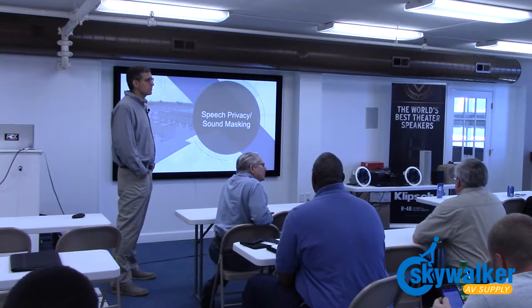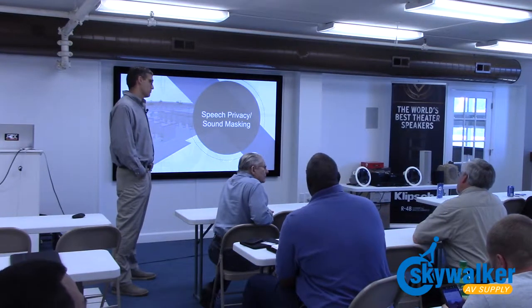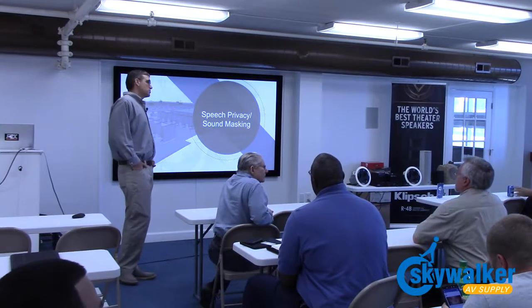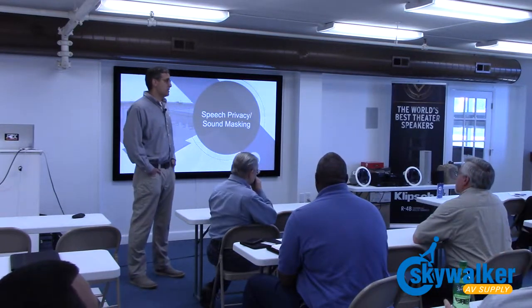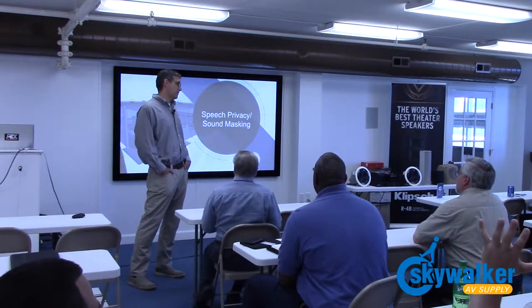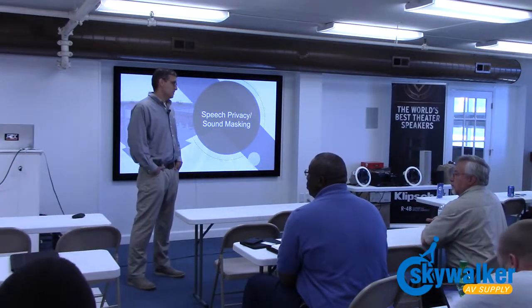When you're talking about the 70 volt there, as opposed to just running low voltage wire to two channels, is that all in the receiver that's doing that? Where is it starting? The amplifier starts with a 70 volt output. Like my amplifier up here on the back, it's got a common, and then it's got an 8 ohm option if you want to run it at 8 ohm, it's got a 70 volt option, it's got a 100 volt option. So you start it at the amplifier, and then it connects to the transformer on the speakers. Okay. So you got to have both.